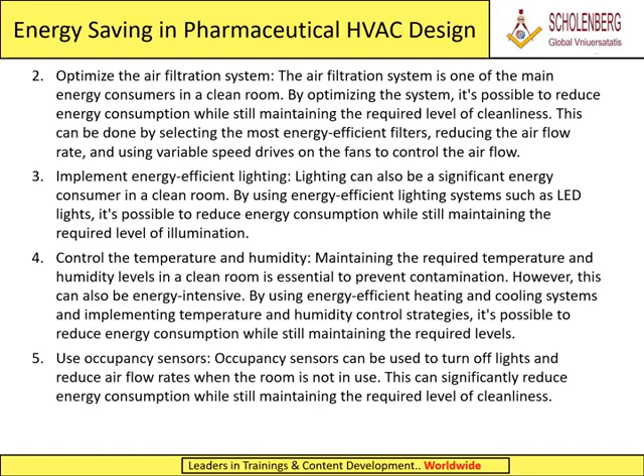3. Implement energy-efficient lighting. Lighting can also be a significant energy consumer in a clean room. By using energy-efficient lighting systems such as LED lights, it's possible to reduce energy consumption while still maintaining the required level of illumination. 4. Control the temperature and humidity. Maintaining the required temperature and humidity levels in a clean room is essential to prevent contamination. However, this can also be energy intensive. By using energy-efficient heating and cooling systems and implementing temperature and humidity control strategies, it's possible to reduce energy consumption while still maintaining the required levels.